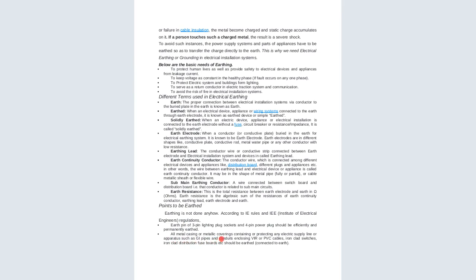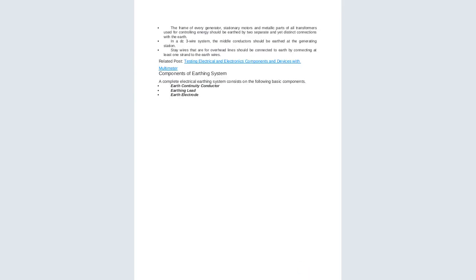All the metal casings and metallic coverings containing or protecting any electric supply line and apparatus, such as the GI pipes and conduits enclosing the VIR or PVC cables, iron-clad switches, and iron-clad distribution fuse boards, should be earthed, that is, connected to the earth. The frame of every generator, stationary motors, and metallic parts of all transformers used for controlling energy should be earthed. I started by saying that all the electrical appliances, installed or not installed, have to be earthed, and should be earthed by 2 separate and distinct connections with the earth.